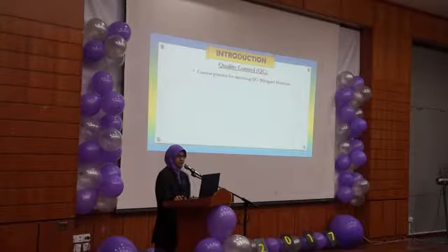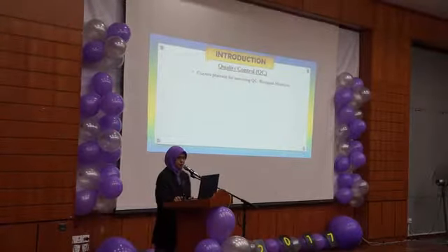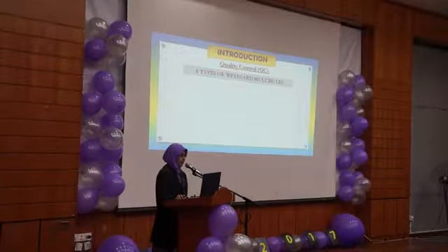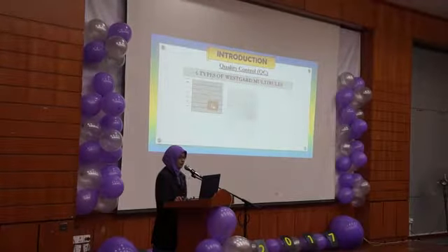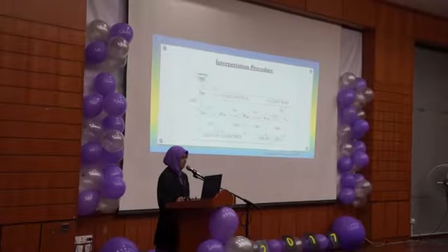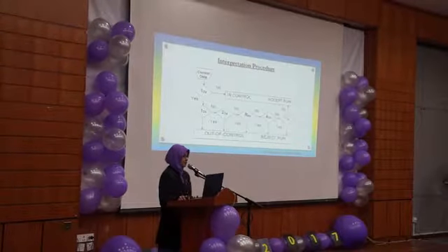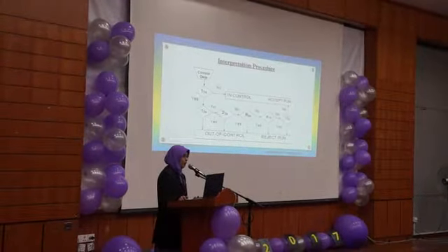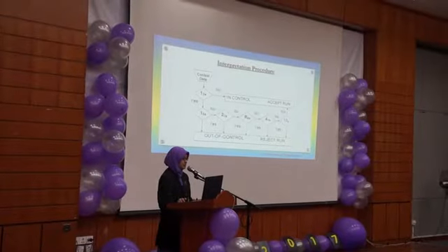The current practice for assessing QC is by using Westgard rules. I think a lot of you are familiar with these. There are 6 types of commonly used Westgard rules, which are 1-2S, 1-3S, 2-2S, R-4S, 4-1S and 10x. The common interpretation procedure is that the QC will be considered in control only if none of these rules are violated.